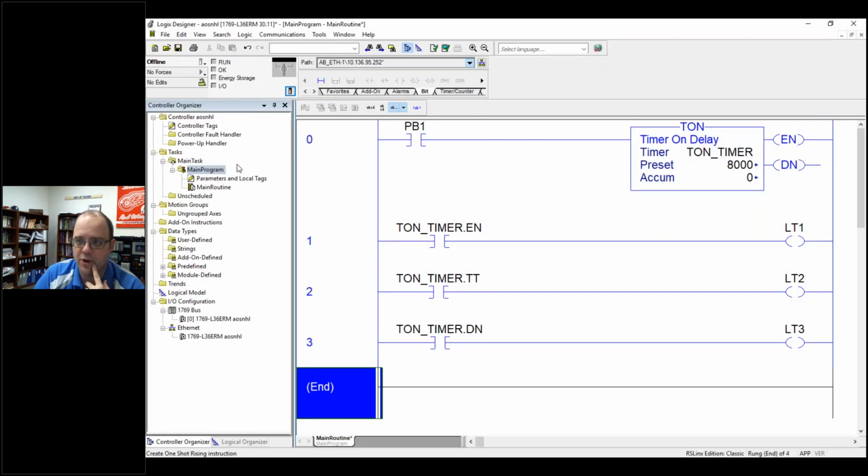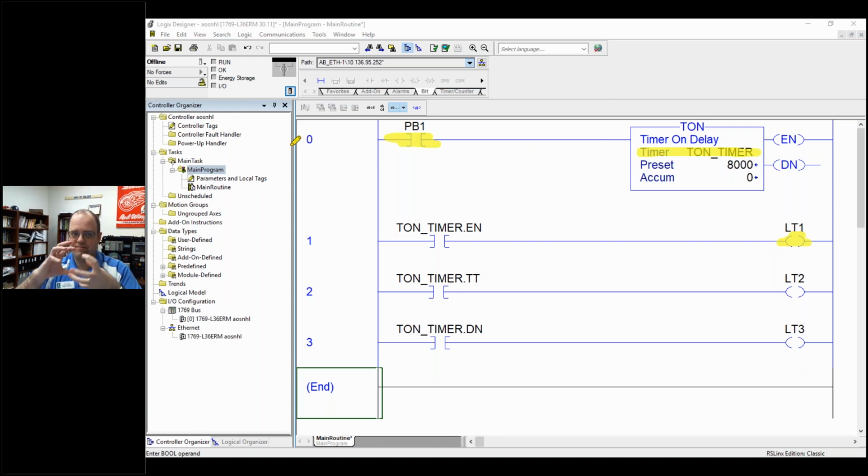Okay, and here's our Allen Bradley software, but the one thing to keep in mind, this is a basic setup of what we would do with a timer setup. Two important things. One, up to this point, we've only been programming with these bits here, and then, of course, the XIC, where they're looking at bools. Bool is the data type. If I have a push button, that's a bool. It's only 0, 1. In this case, though, we have its own data type that we use for timers, because a timer utilizes kind of a package of data types.